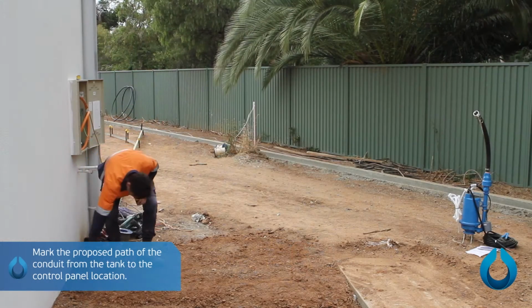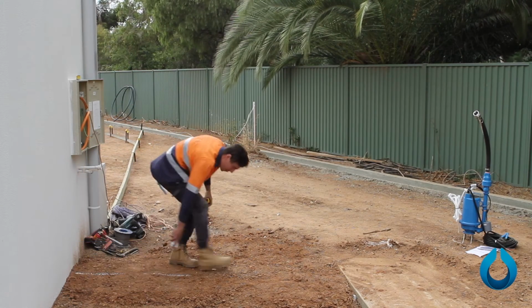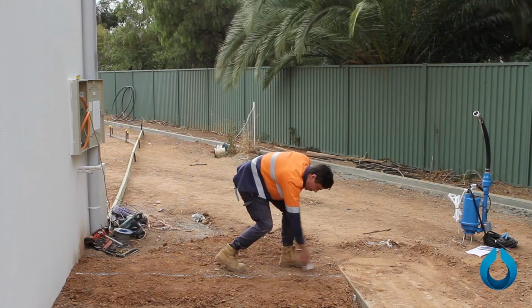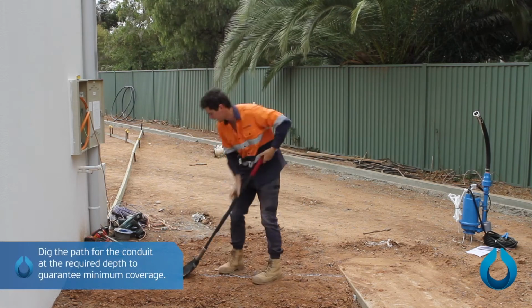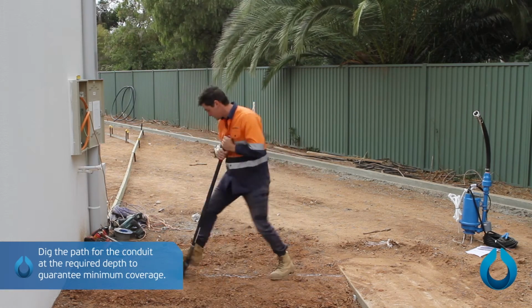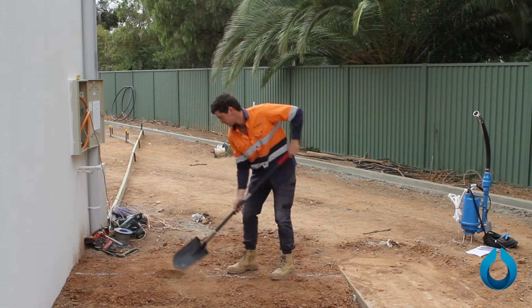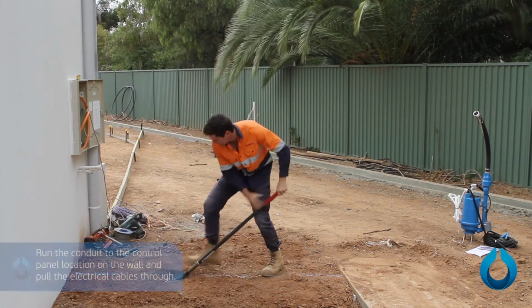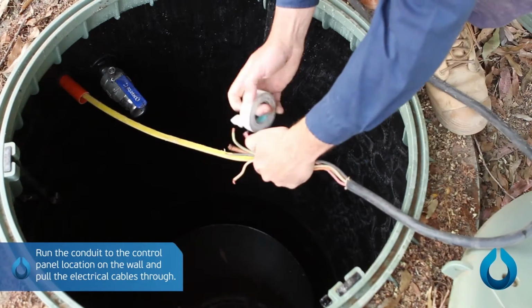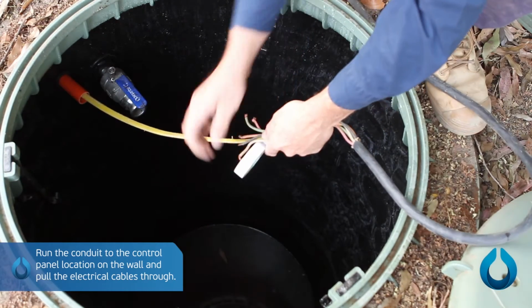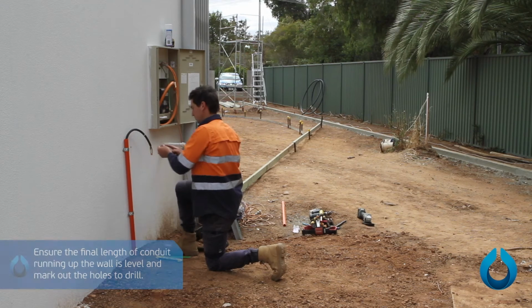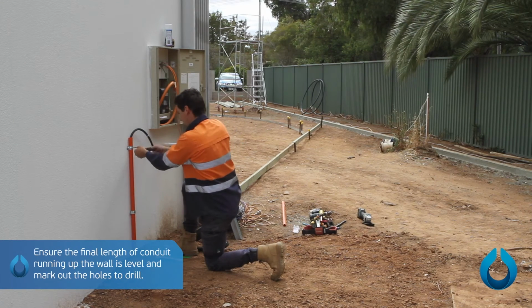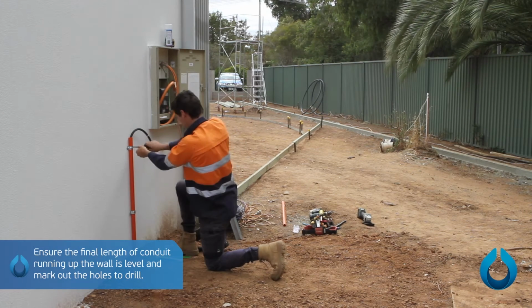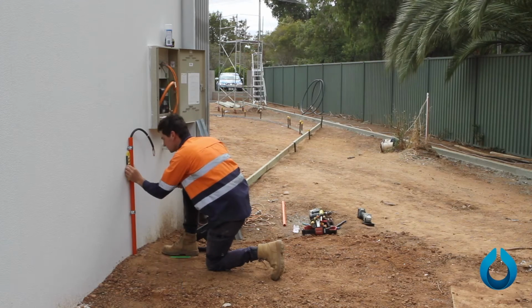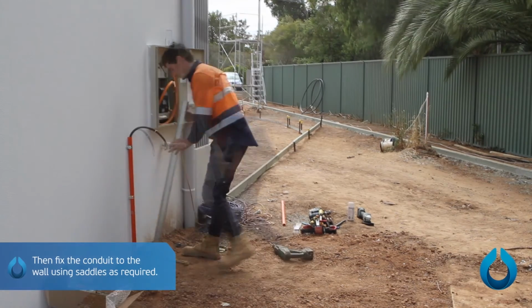Mark the proposed path of the conduit from the tank to the control panel location. Dig the path for the conduit at the required depth to guarantee minimum coverage. Run the conduit to the control panel location on the wall and pull the electrical cables through. Ensure the final length of the conduit running up the wall is level and mark out the holes to drill, then fix the conduit to the wall using saddles as required.